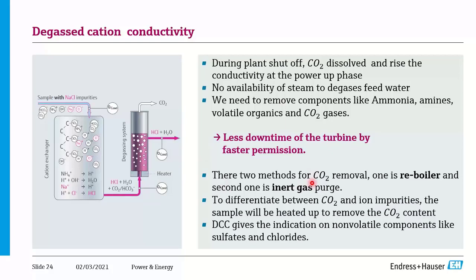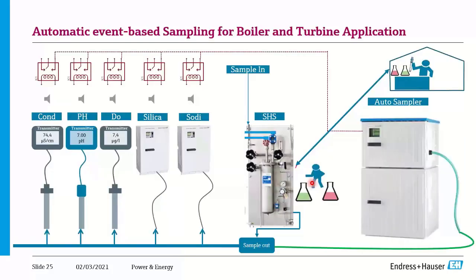We also have degassed conductivity for boiler startup operations. Additionally, consider automatic event-based sampling for boilers and turbines. Instead of lab personnel collecting samples on a regular routine, you set up events in your analyzer — for example, when silica content goes high or pH drops below 9, the analyzer triggers the sampler to collect a sample automatically. This avoids regular manual sampling and enables cross-verification with the laboratory only when an event occurs.